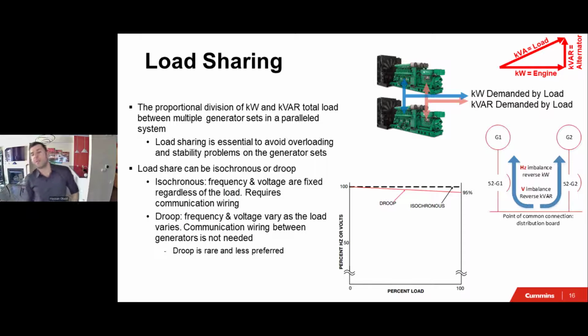Your loads will demand from both. Your loads are not completely resistive and they're not completely reactive, right? So a lot of times you need to provide both real and reactive power. Typically the engine is where the real power comes from and the alternator is where the reactive power comes from. Load sharing is dividing that load equally amongst the generators. If we don't do that, we will have problems with stability of the generators.